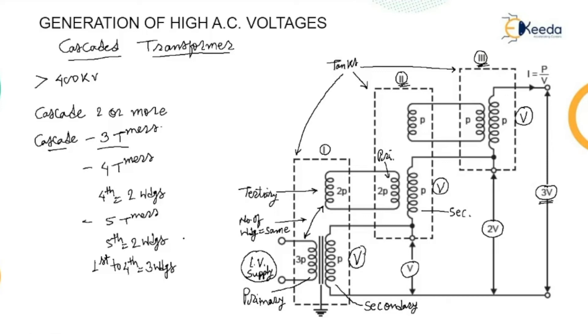The uppermost will be a 2-winding transformer. In the metal tank construction, the low voltage terminal of the secondary winding is connected to the tank. The tank of stage 1 transformer is earthed. The tanks of stage 2 and stage 3 transformers have potentials of V and 2V respectively above earth, and therefore must be insulated from earth with suitable solid insulation. Through high tension bushings, the leads from the tertiary winding and high voltage winding are brought out to connect to the next stage transformer.